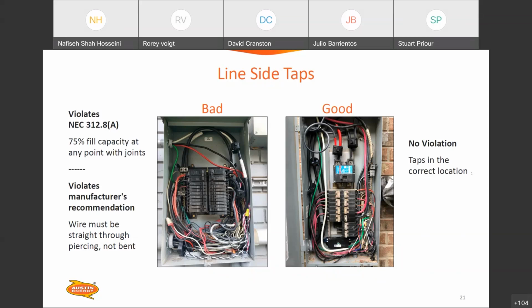A good rule of thumb: if you can put that dead front in and close it without putting any stress on it, you'll probably be fine. The left situation would likely require a service upgrade, while the one on the right shows how to do it correctly. You want your taps in a clear spot at the top or bottom of the panel, with plenty of working room, and they need to tap the service conductors in a straight length of conductor, not at a bend.